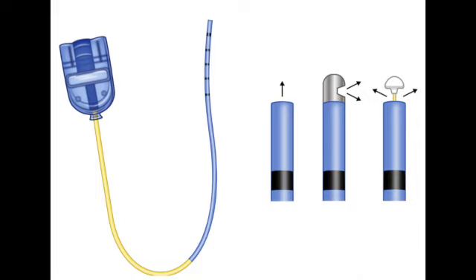The argon gas flows out, and the electrical current ionizes that gas right as it exits the catheter. Ionizes it, turns it into what? It turns it into plasma. Think of plasma as like a super energized conductive gas. It's that argon plasma beam that actually carries the electrical energy across the small gap, maybe just a few millimeters from the catheter tip to the tissue surface. So the plasma jumps the gap. It literally does. And when that plasma hits the tissue, the electrical energy converts to heat. And that's what causes the coagulation or the ablation effect. And because it's a plasma beam, it can spread out a bit. It does. It spreads laterally, which is great for treating broader, flatter areas, unlike just touching a point with a hot probe.